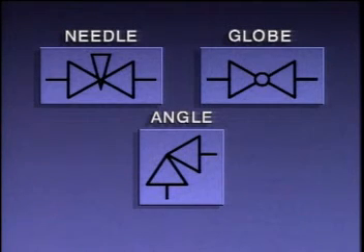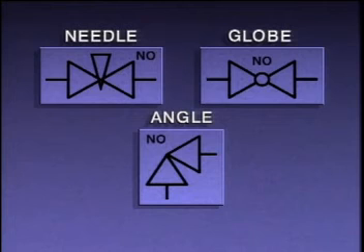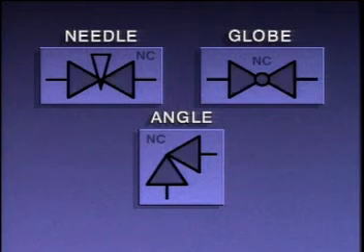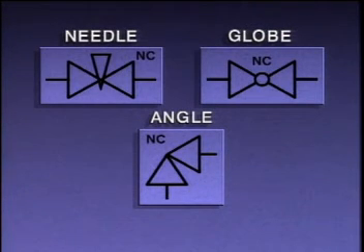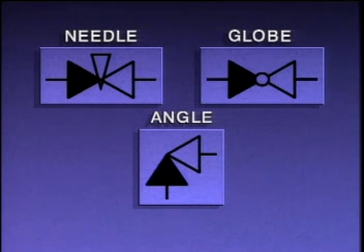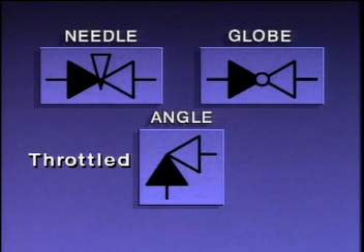If the symbols look like this or have the letters NO beside them, the valves are normally open. If the symbols are filled in or have the letters NC beside them, the valves are normally closed. The symbol may also be shown partially filled in. When the symbol is shown this way, the valve is in a throttled position.